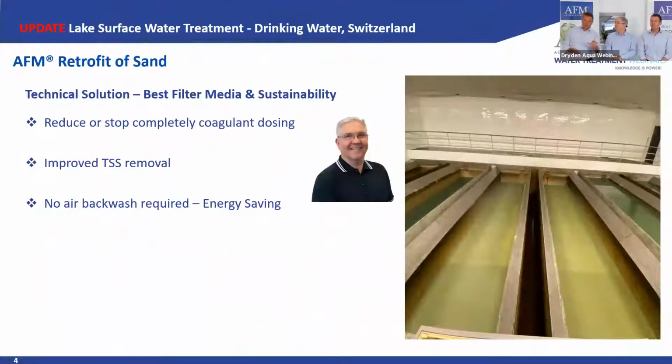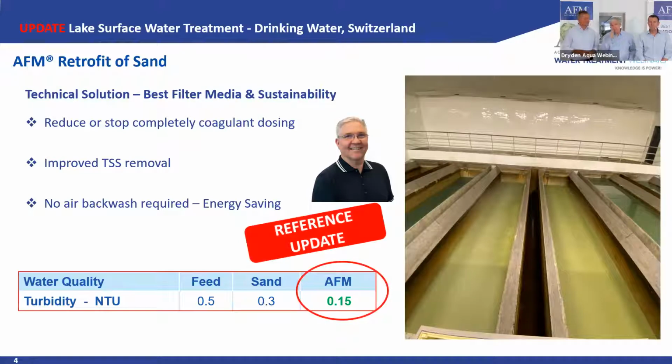This is not wastewater. This was drinking water. I just want to give you a quick update here. In our last webinar we presented this case study. We said it had just gone into operation, but there were no figures. Now we have first figures, and I'm really impressed. They started at 0.5 NTU, and then we reached 0.15, measured just two days ago. I'm really excited about these results.